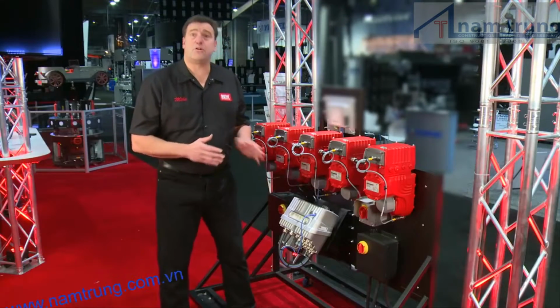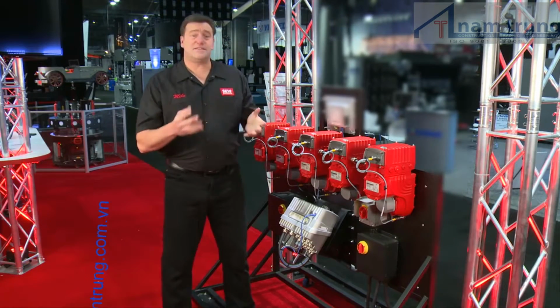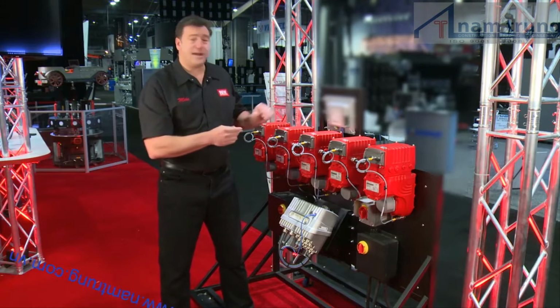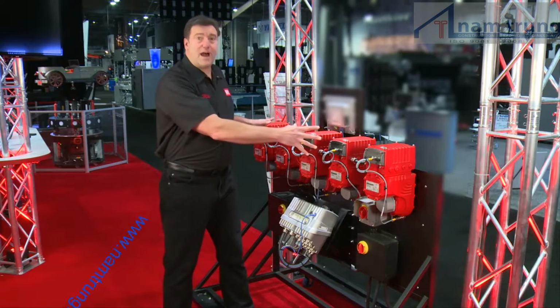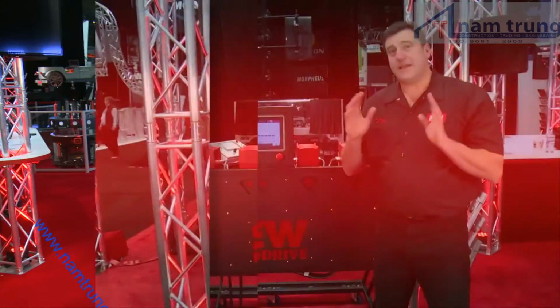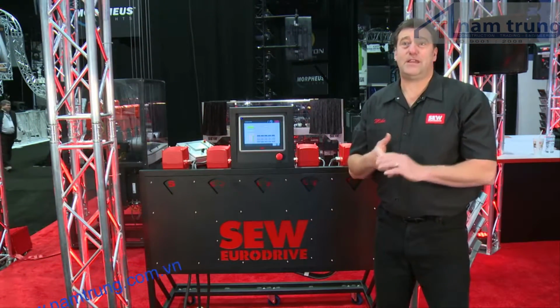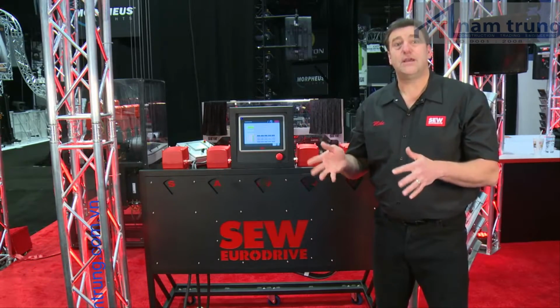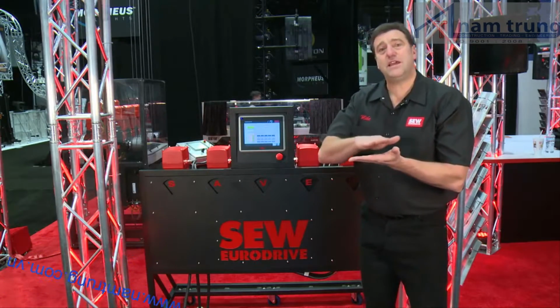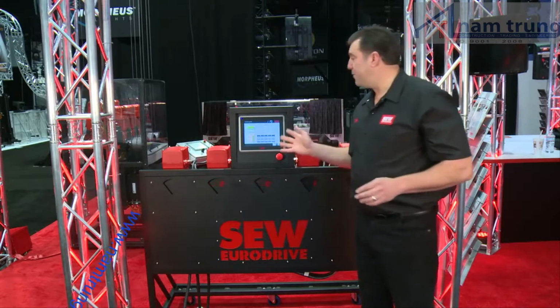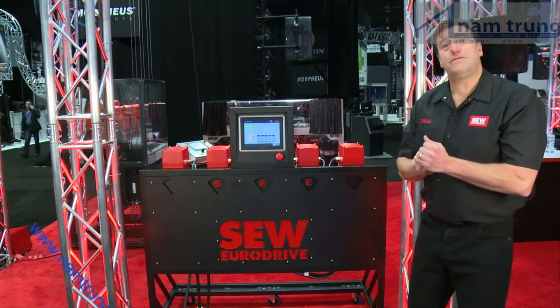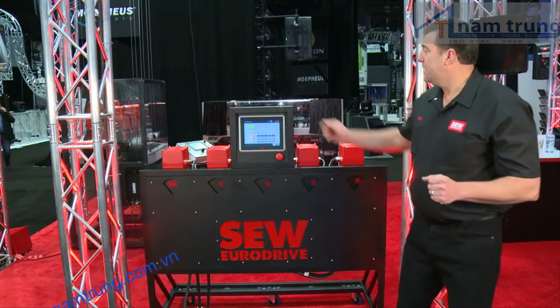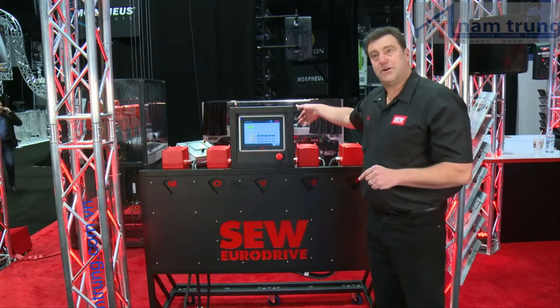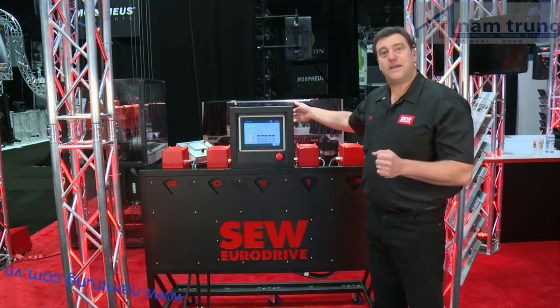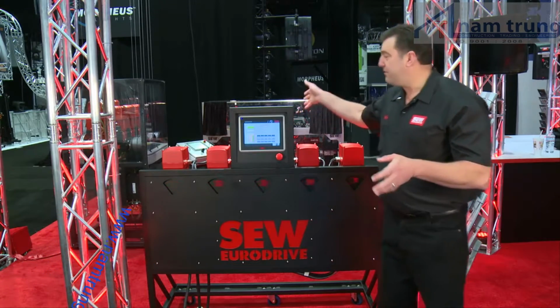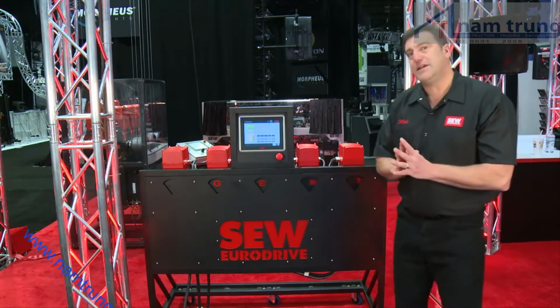The FDC controller also has a built-in PLC. This allows me to program this application using my SNI network. I can control these 5 MOVIGEARs using positioning control. The SEW MOVIGEAR has the capability of doing linear and modulo positioning. Modulo positioning is continuous rotation, but we don't accumulate error. Therefore, in this application, we can go every 35 degrees and pull up a different letter. We can enter data through our touchscreen to our FDC controller, which houses our PLC. PLC logic then, over the SNI network, controls these MOVIGEAR units.